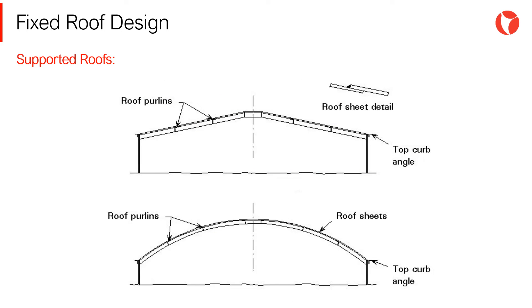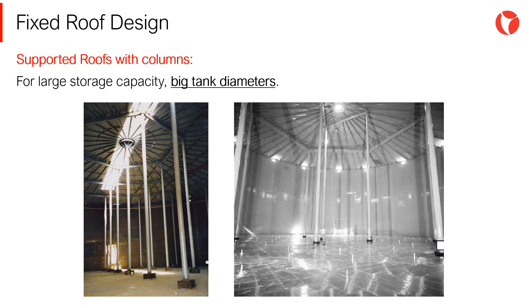This type of roof consists of a set of overlapping welded plates supported by a structure on which the roof plates rest. The structure is formed by a system of rafters and purlins which are attached to the tank shell, and this structure will be designed to withstand all acting loads. In addition to rafters and purlins, and due to the size of the roof, it is necessary to use intermediate beams which will form regular polygons or circles.